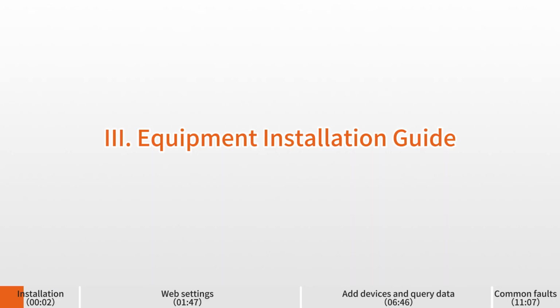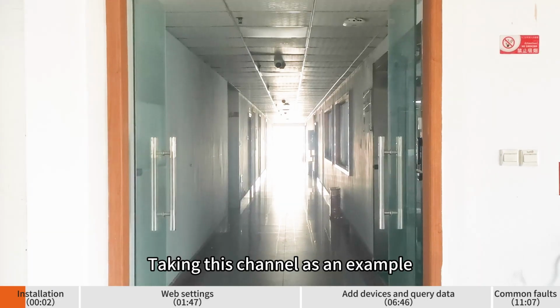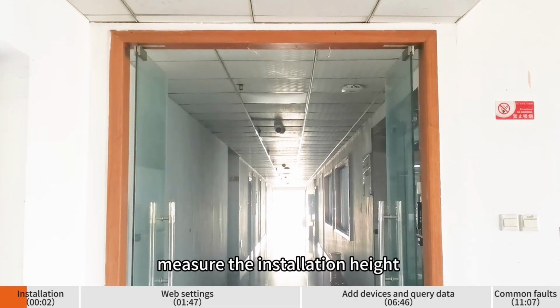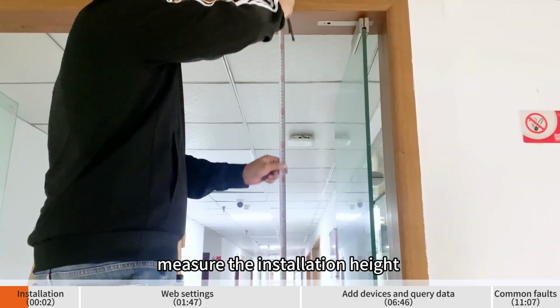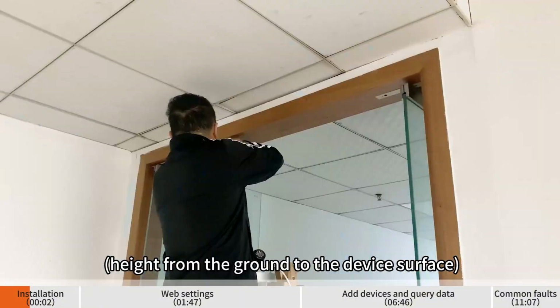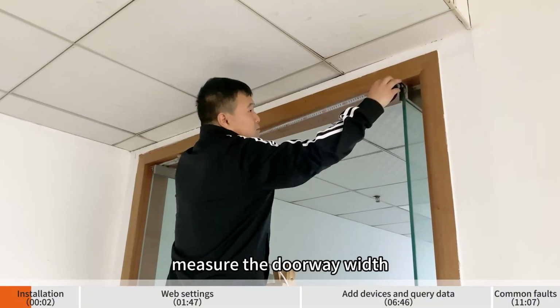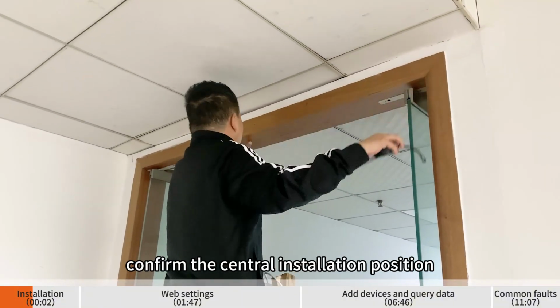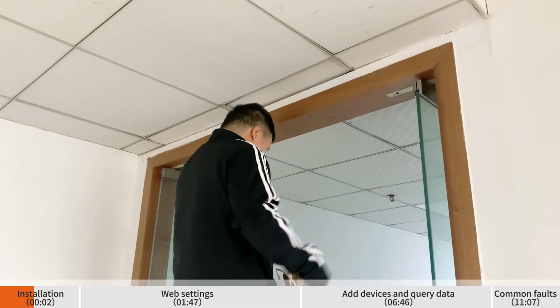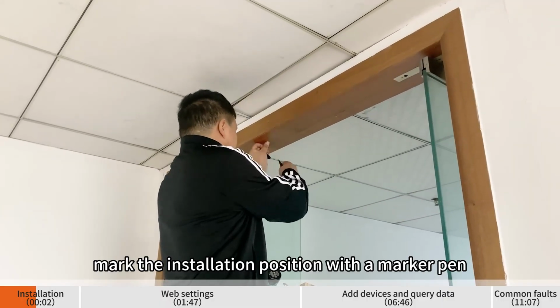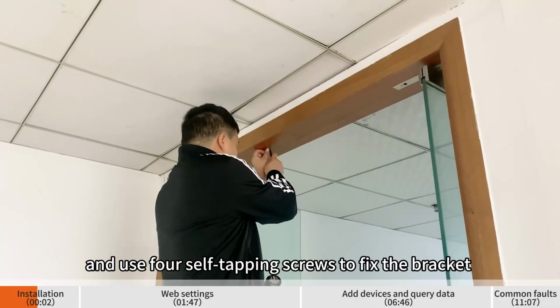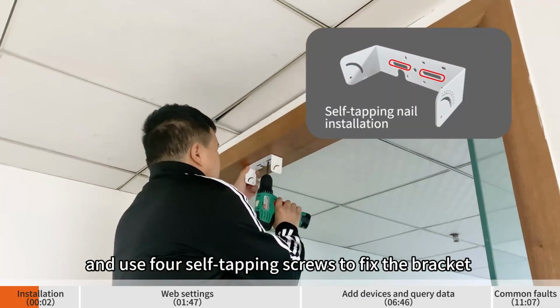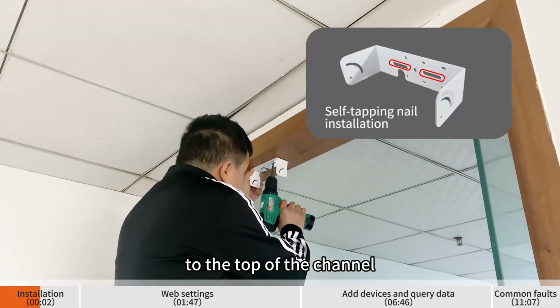3, equipment installation guide. Taking this channel as an example, measure the installation height from the ground to the device surface. Measure the doorway width, confirm the central installation position, mark the installation position with a marker pen, and use 4 self-tapping screws to fix the bracket to the top of the channel.